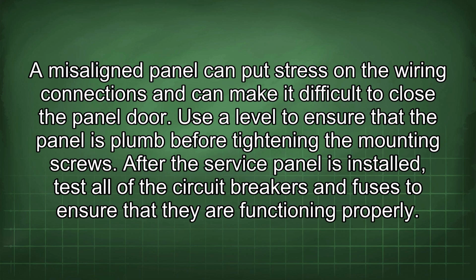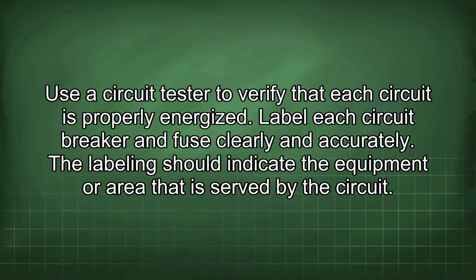After the service panel is installed, test all of the circuit breakers and fuses to ensure that they are functioning properly. Use a circuit tester to verify that each circuit is properly energized. Label each circuit breaker and fuse clearly and accurately. The labeling should indicate the equipment or area that is served by the circuit.